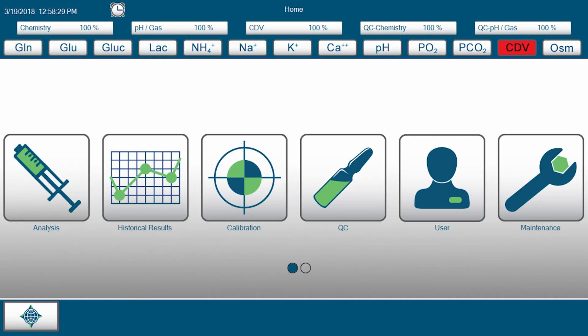The module for the parameter is not primed with the required reagents. The module for the parameter is not connected to the internal computer. The parameter is unavailable due to a dependency on another unavailable parameter. For example, if the glutamate parameter is not available, the glutamine parameter icon will also be red, and glutamine unavailable. System intervention is required. In the case of the osmometer, the Osmo status icon will turn red when there are no longer any unused tubes remaining on the Osmo tray for sampling.